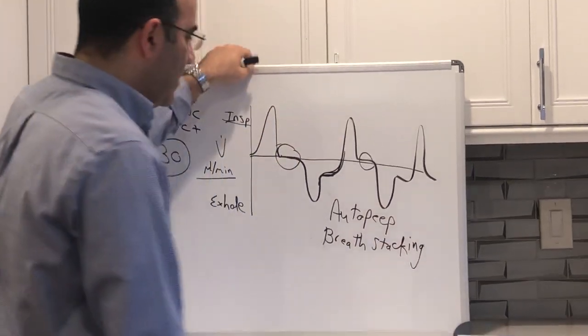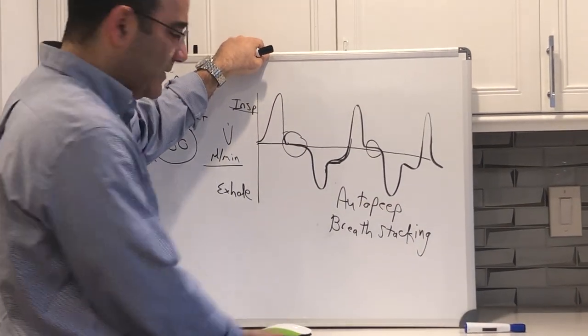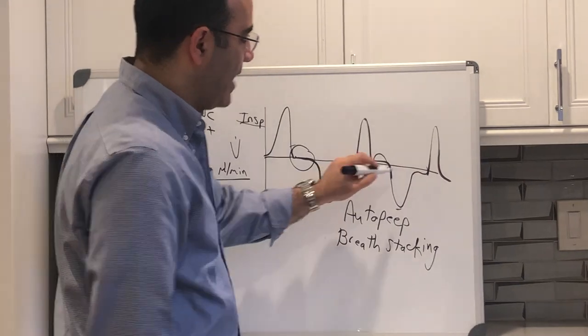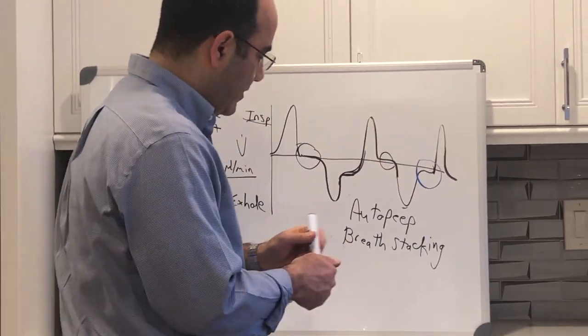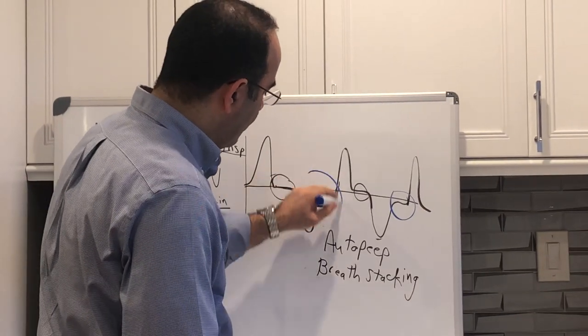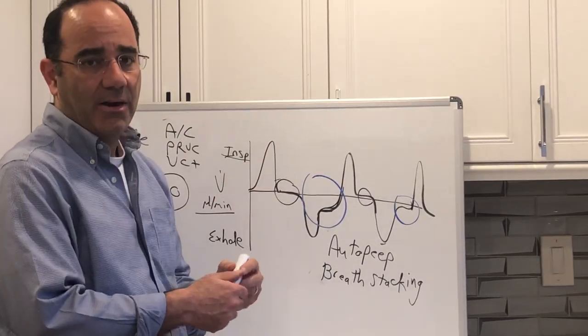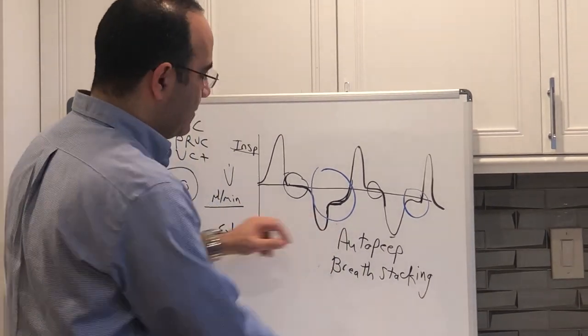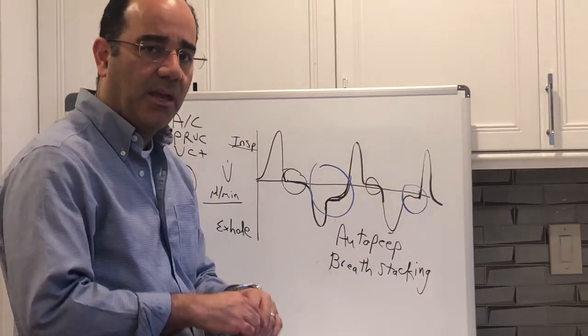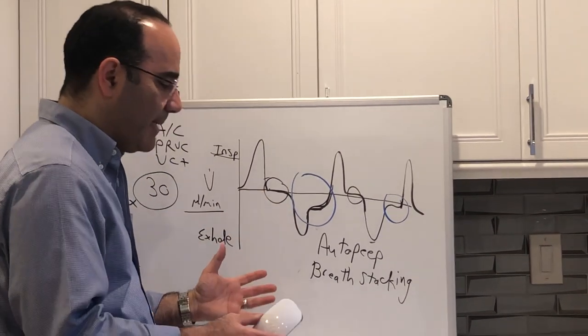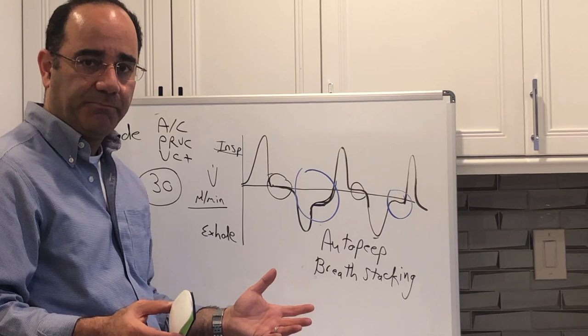Does it matter? Maybe, maybe not. If you have a little bit of auto-peep, it probably doesn't matter. But if you have a big degree of auto-peep, that may matter. You can only go so high on the respiratory rate. Once you start seeing auto-peeping, that's about the limit. You need to start backing down a little bit, and that might cost you some acidosis, but it is what it is.